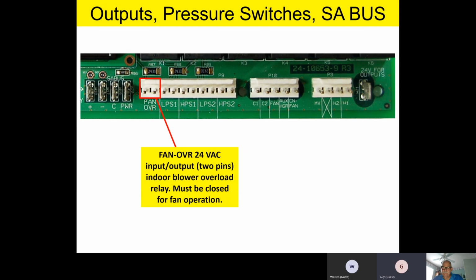Joe, when that typically faults, you're able to do a test through the VFD to see what type of fan it's in, correct? So if you take a look at our fan motors, you're going to notice there's a little thermal disc on there. They call it a blower overload relay, but it's just a little thermal disc. If it overheats, it's going to open electrically and shut the fan down. Or if the VFD has a thermal problem, it'll hit that fan overload, and then it'll drop out that little fan pin that we talked about earlier that outputs that 24 volts for fan operation. So this fan overload is strictly a safety circuit, and it's just a little thermal disc on the fan motor itself. You're going to notice, hey, what are those two little wires off the back there by themselves? I think they're purple wires. That's the fan overload.